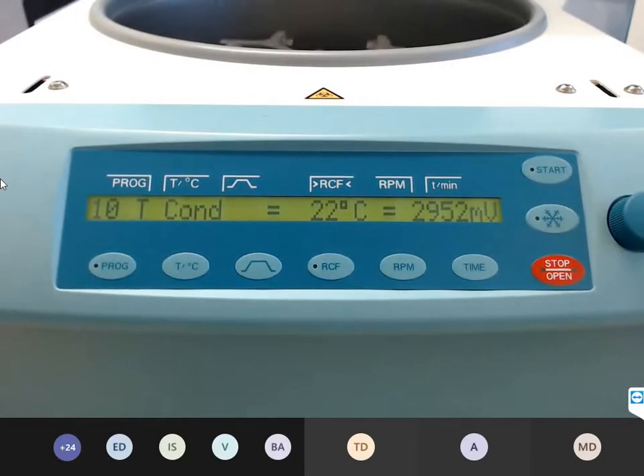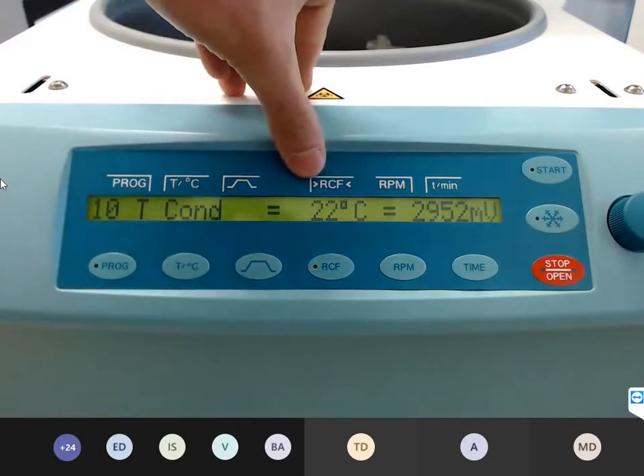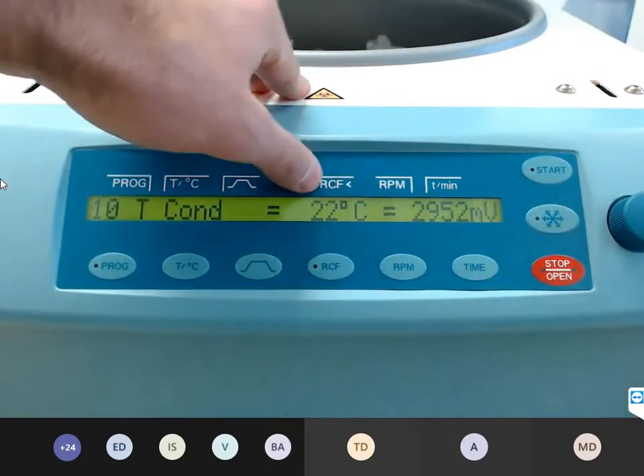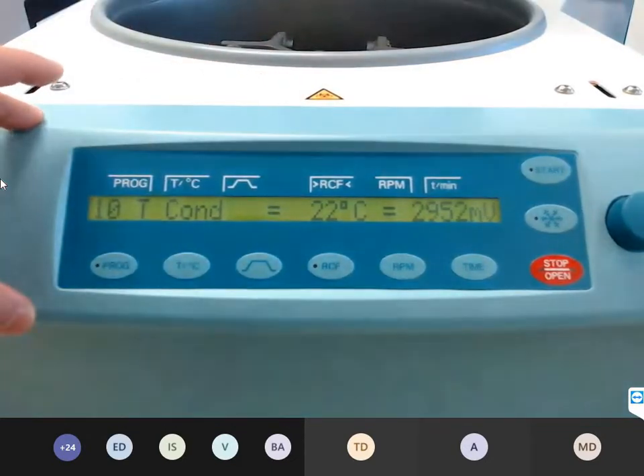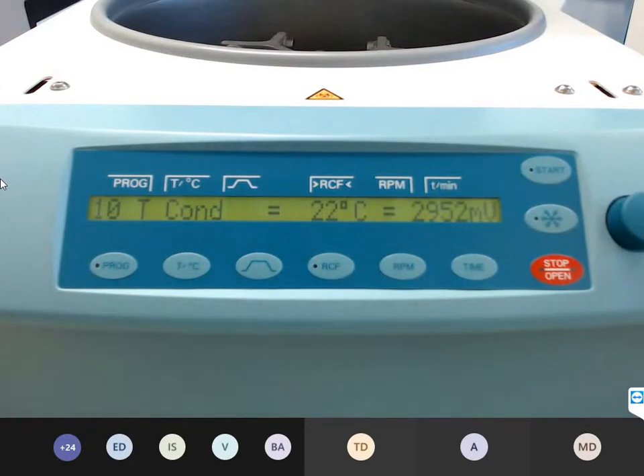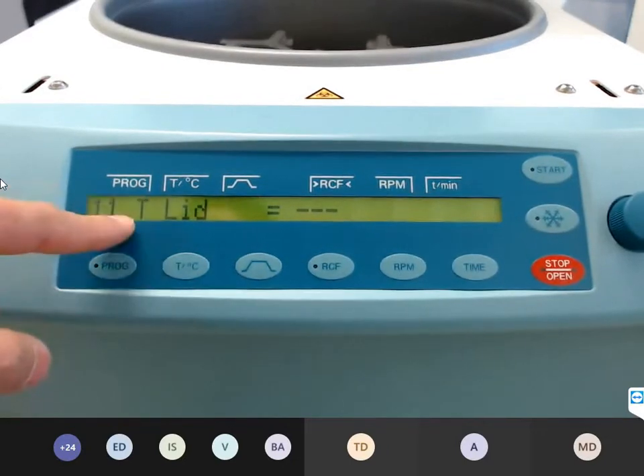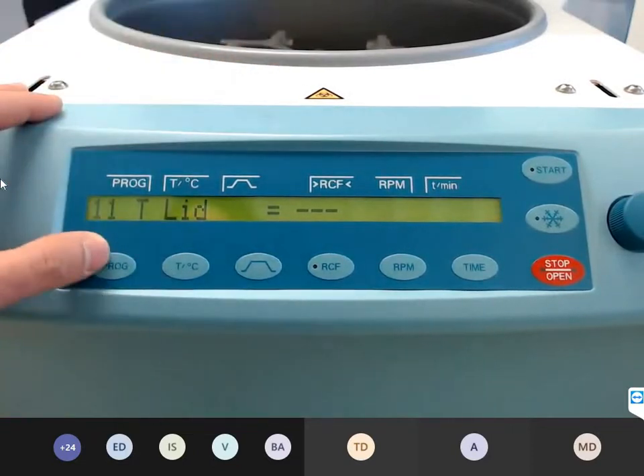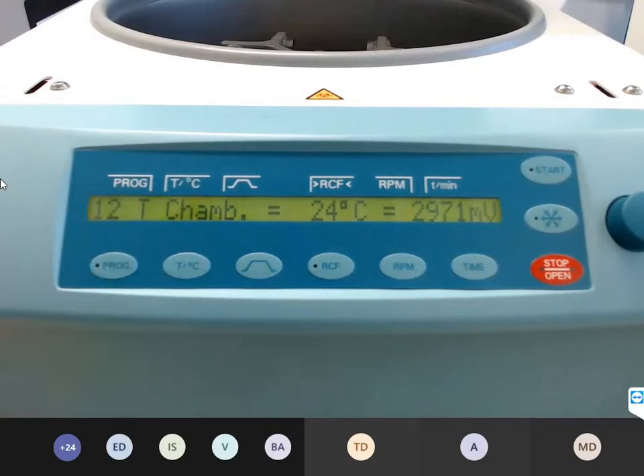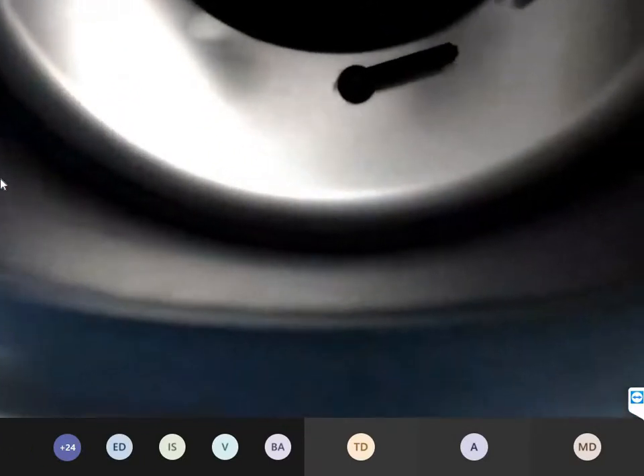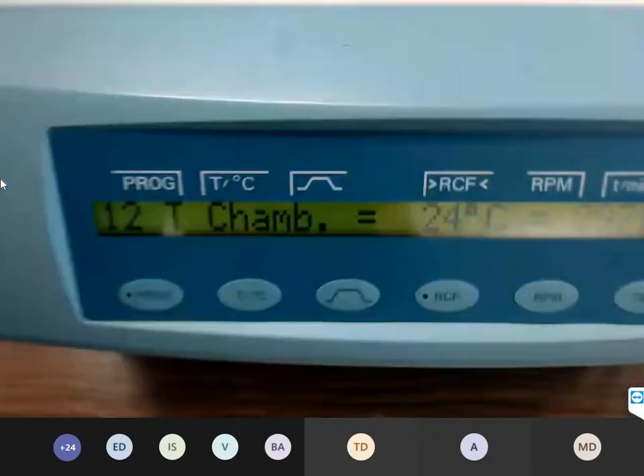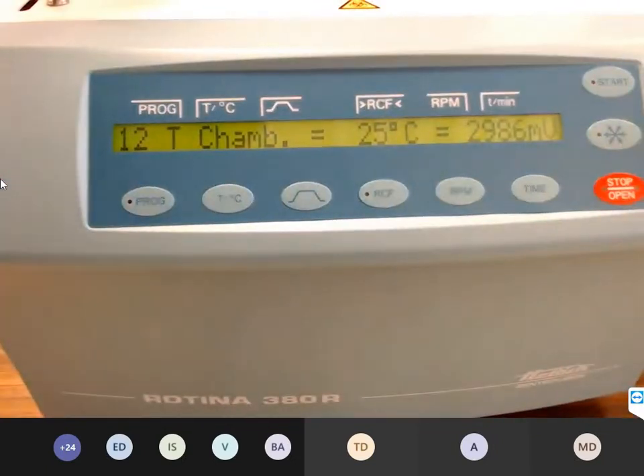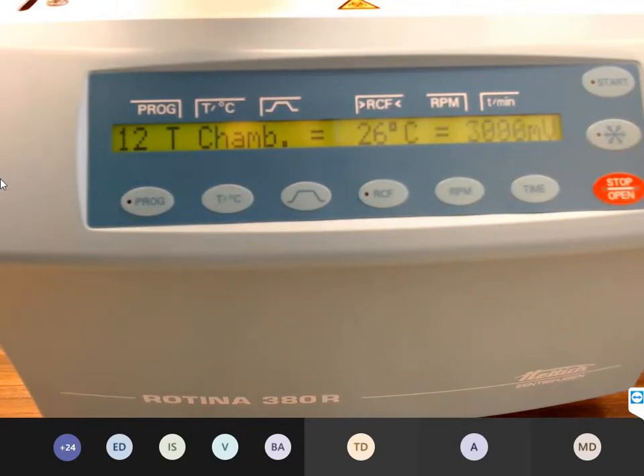So, the temperature on the condenser. We have a condenser temperature sensor. This is the temperature now at the condenser. The device calculates it in millivolts automatically. We don't have a temperature sensor on the lid. The temperature sensor on the chamber, you can test it. Hold this one with your hands or fingers, and then you can see the temperature goes up, goes down. Yes, goes up. 26. It works.